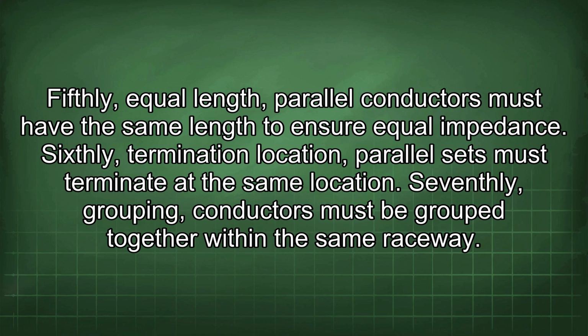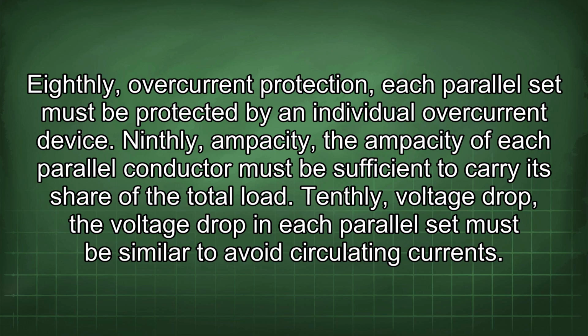Sixthly, termination location. Parallel sets must terminate at the same location. Seventhly, grouping. Conductors must be grouped together within the same raceway. Eighthly, overcurrent protection. Each parallel set must be protected by an individual overcurrent device. Ninthly, ampacity. The ampacity of each parallel conductor must be sufficient to carry its share of the total load. Tenthly, voltage drop. The voltage drop in each parallel set must be similar to avoid circulating current.